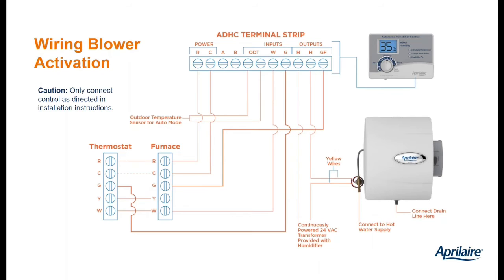At the humidistat, you've got a G as an input and a GF as an output. Let's follow those wires back. Let's start with the G at the humidistat. So G up top, let's follow that wire down, and you can see that that goes to the thermostat. So what are we doing? Well, look at the G between the thermostat and the furnace. That's disconnected. So that's the only change we've made so far. So at the HVAC system, you've got a G coming from the thermostat. Disconnect that, hopefully green wire, and we're going to extend that green wire to G on the humidistat. So you probably have to add a wire nut and add a wire to get from that G that was landed at the furnace. Now we're just going to land it at the G on the humidistat.